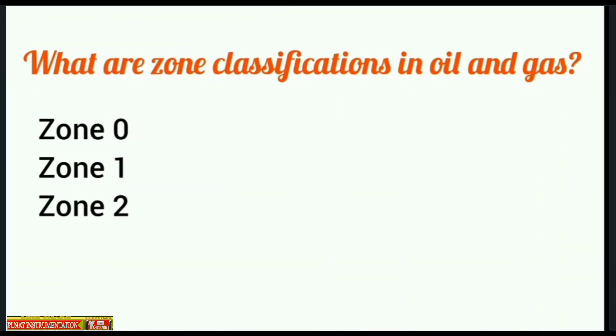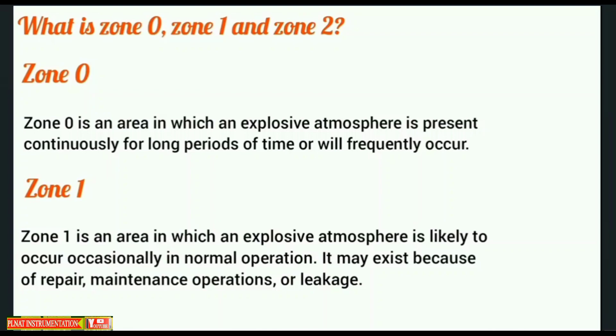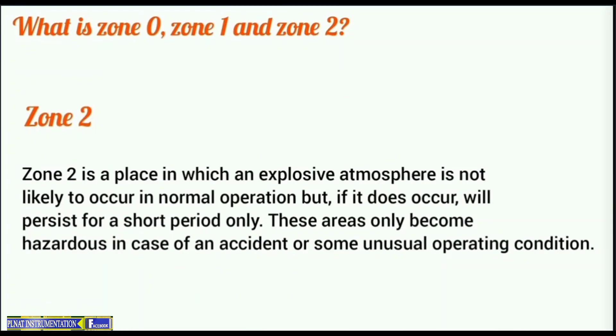What are the zone classifications in oil and gas? Zone 0, Zone 1, Zone 2. Zone 0 is an area in which an explosive atmosphere is present continuously, for long periods of time, or will frequently occur. Zone 1 is an area in which an explosive atmosphere is likely to occur occasionally in normal operation. It may exist because of repair, maintenance, operation, or leakage.